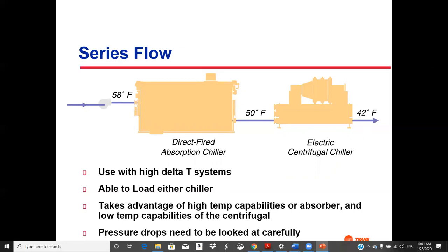One of the advantages of this is that these absorbers have more capacity if you give them warmer water. And so this might be a 1,000-ton chiller, but if I can get 58-degree water, that 1,000 tons would be based on like 54. If I can put 58-degree water in this, I can probably get 1,100 or 1,200 tons of cooling out of it because I'm not pulling it down. And then you take a big chunk of the cooling here, and then you finish it off with the centrifugal. So that's a possibility.